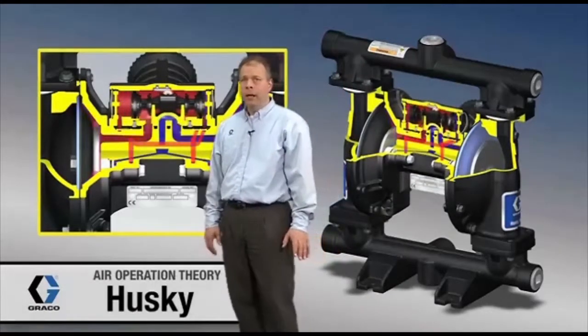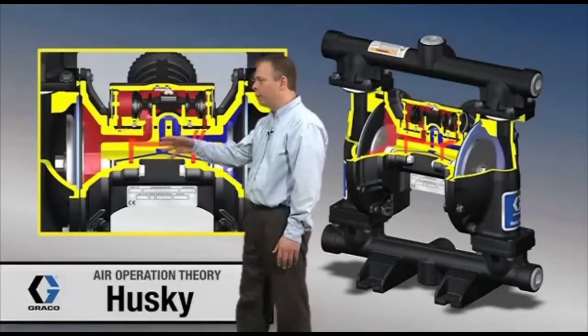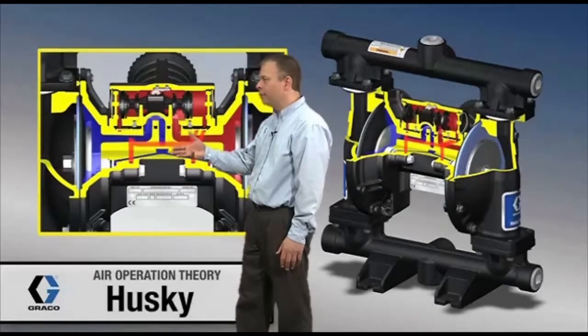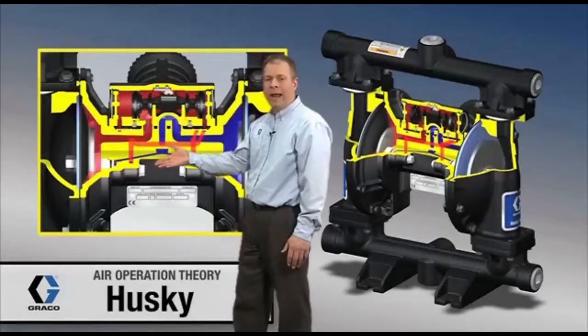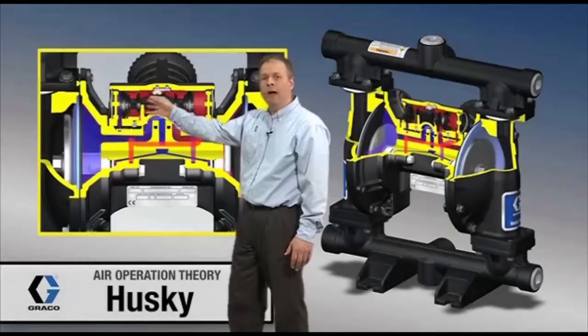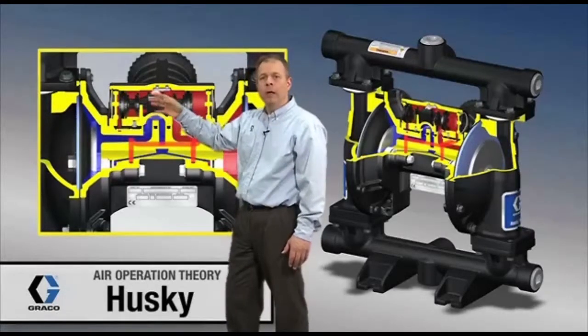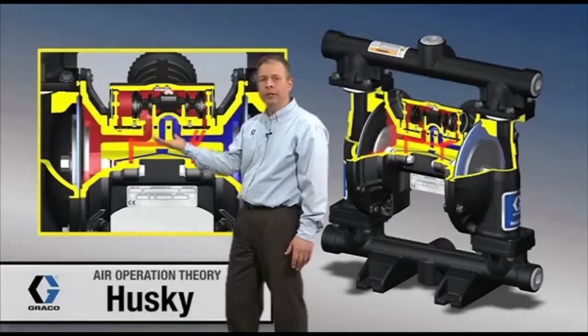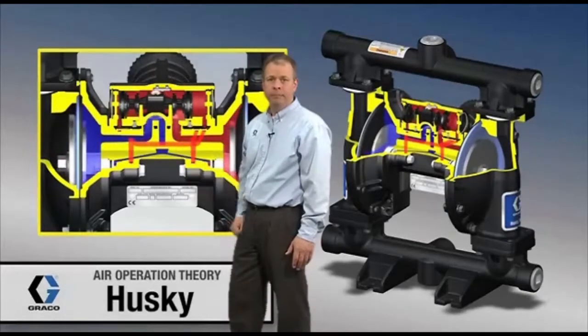Basically what's going on is we're putting air pressure on one side and vent on the other. The diaphragms come in contact with the poppet valves, and that action causes the spool valve up in this module to move back and forth — all it's doing is directing air pressure and vent from one diaphragm to the other.